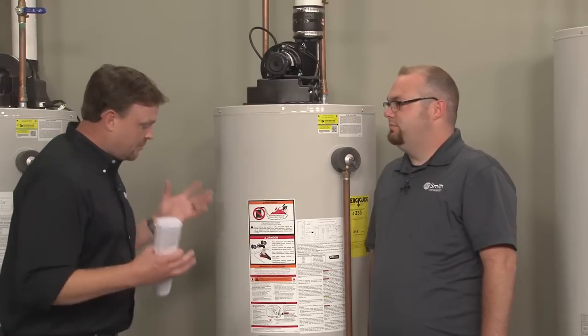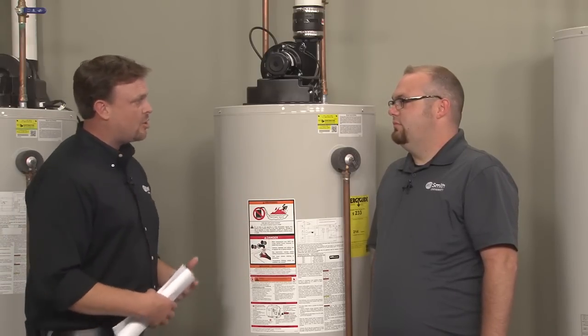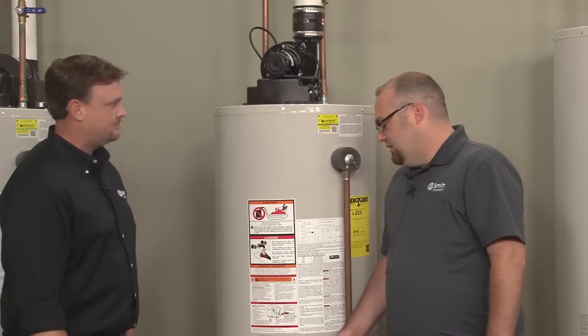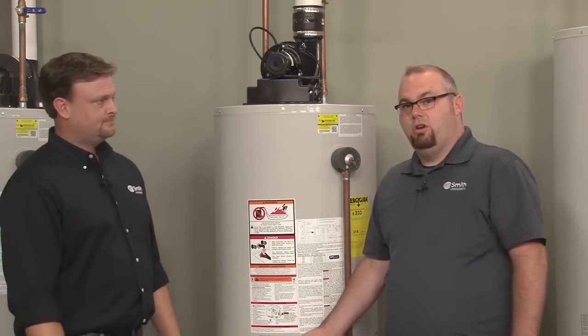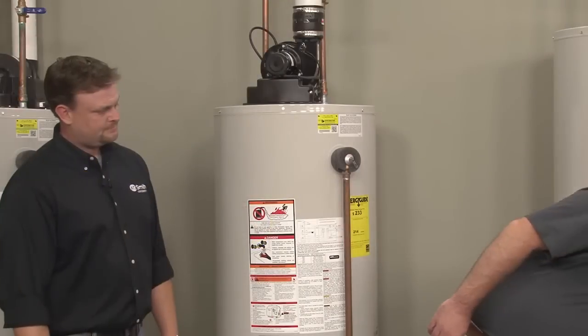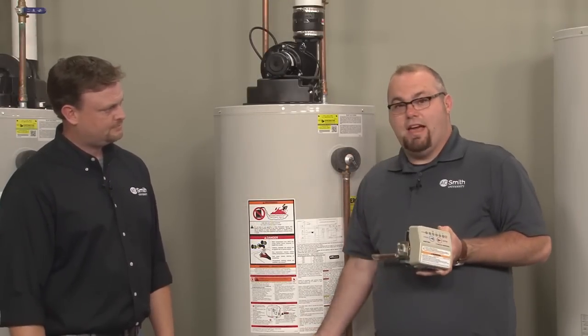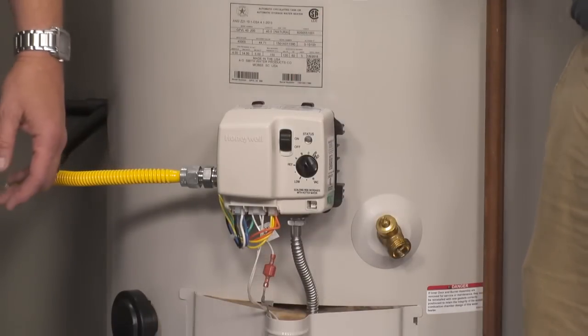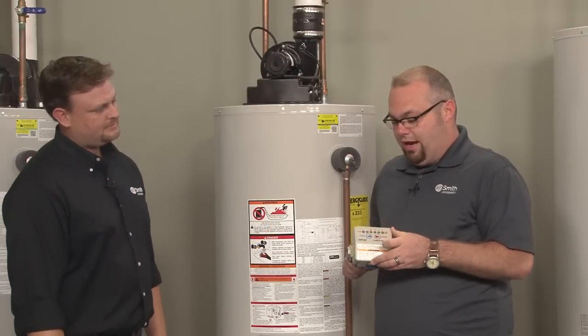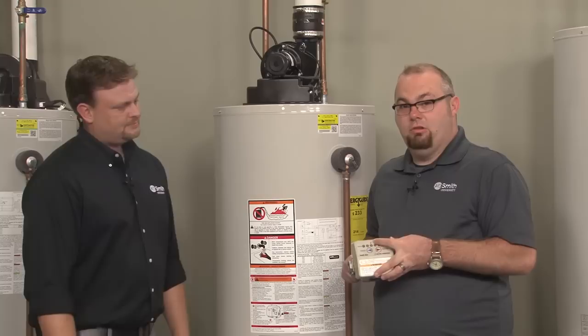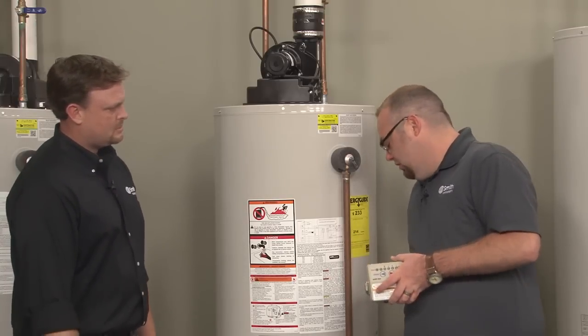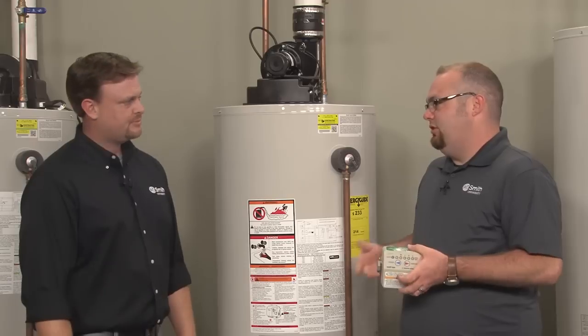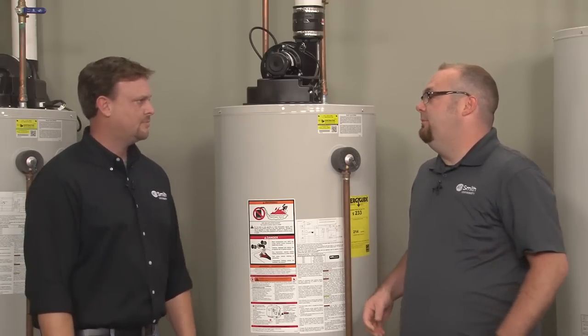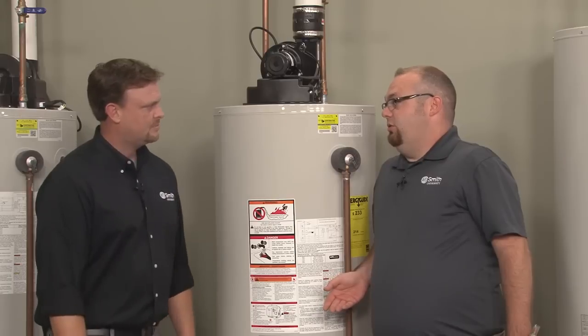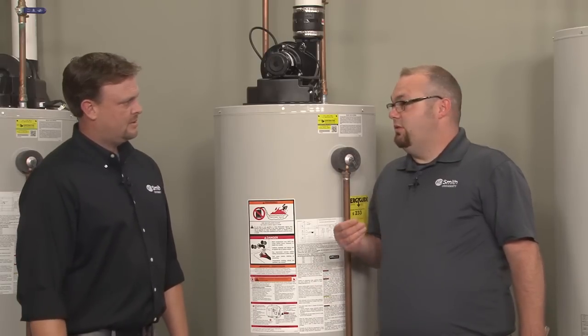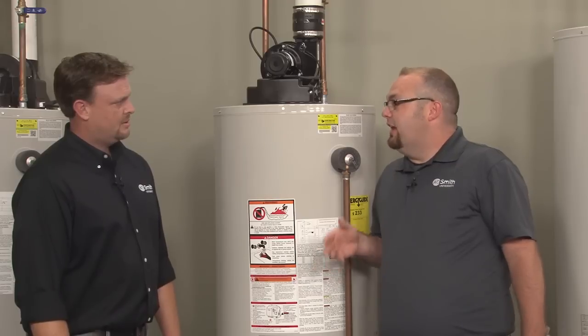Yes. So the first one we're going to talk about is an error code 3. It's 3 blinking lights. It's going to be a 3 flash on the Honeywell controller. But on the IntelliVent control valve, you're going to have the warm light lit up or the vacation light, the triangle, and the C light. Both of these codes, whichever way it's delivered to you, are telling you that the air pressure switch didn't close. And so the heater did not go on with the sequence of operation to heat water. It stuck at that point.